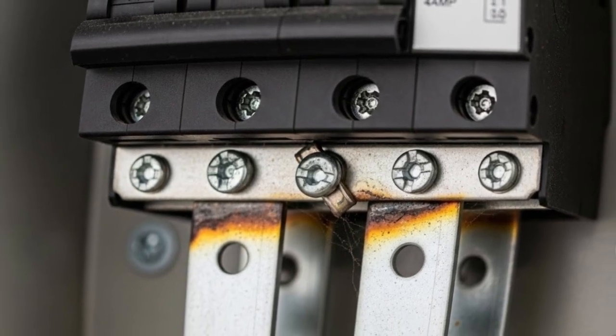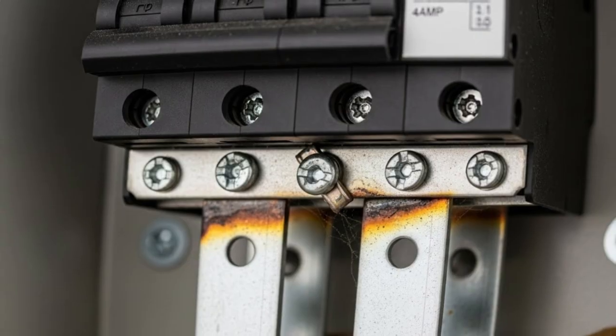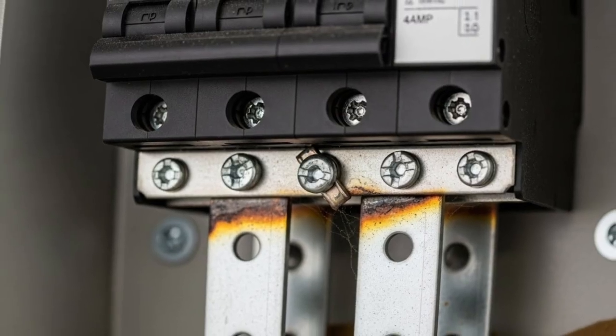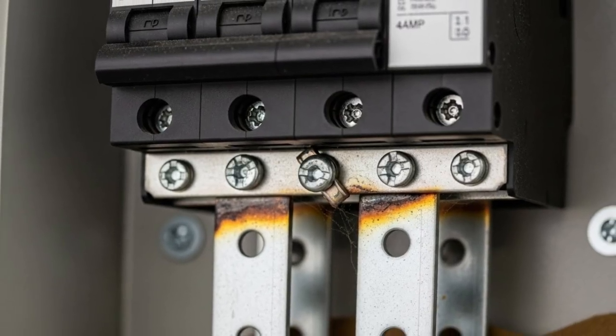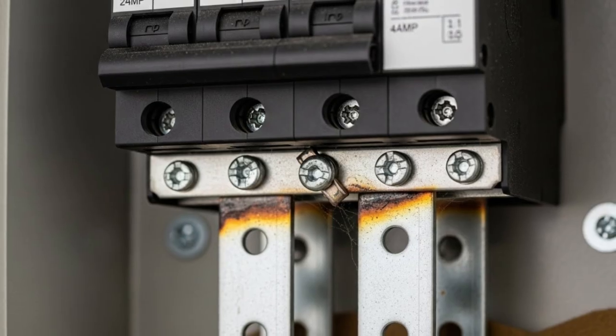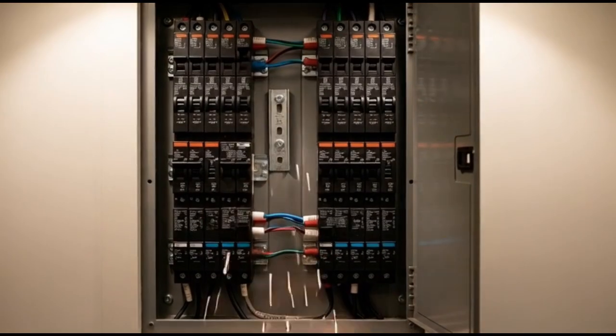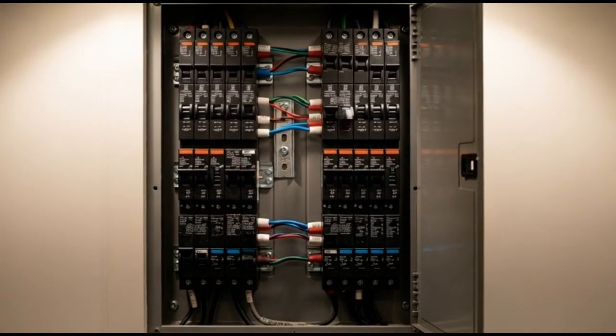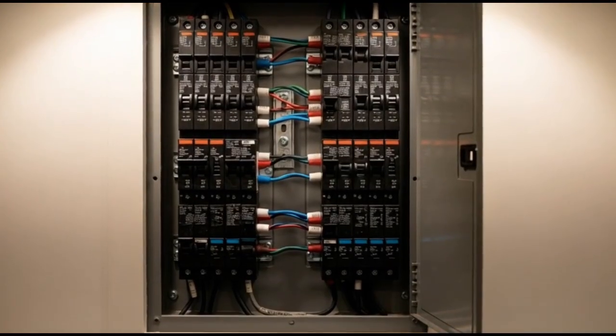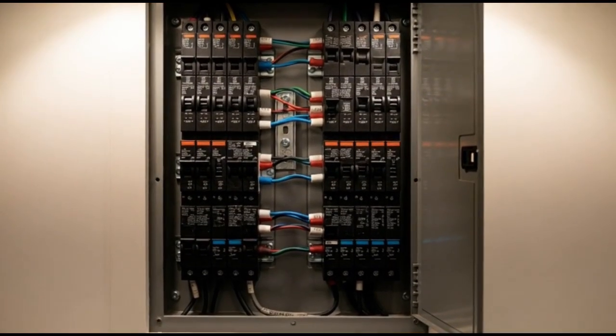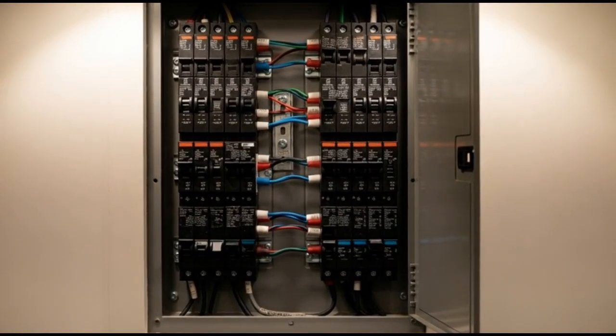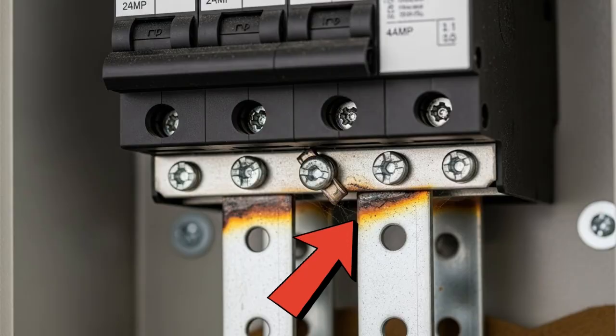A loose bus bar connection creates resistance. Electrical current flowing through a loose connection generates heat instead of flowing smoothly. That heat builds up. The main breaker senses this abnormal condition and trips to protect the system. From the outside, everything looks fine. You're not running heavy loads. But inside the panel, a dangerous hot spot is forming every time current flows through that loose connection.